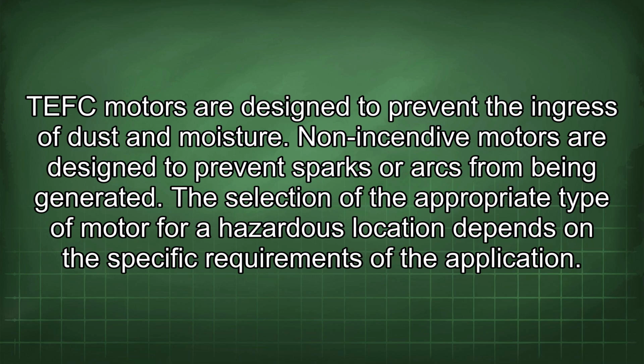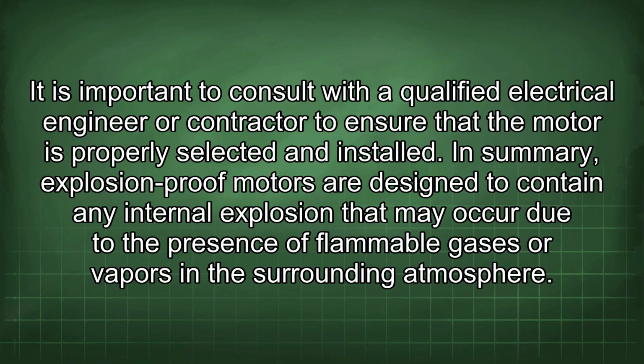TEFC motors are designed to prevent the ingress of dust and moisture. Non-incendive motors are designed to prevent sparks or arcs from being generated. The selection of the appropriate type of motor for a hazardous location depends on the specific requirements of the application. It is important to consult with a qualified electrical engineer or contractor to ensure that the motor is properly selected and installed.